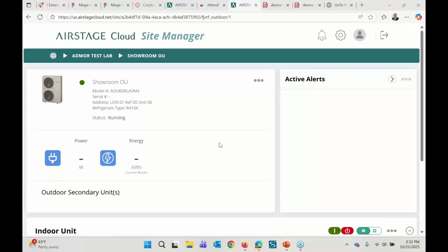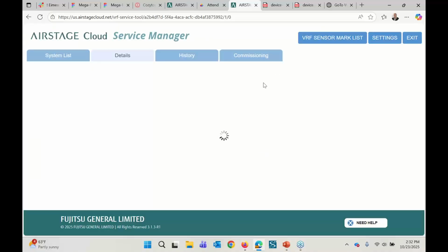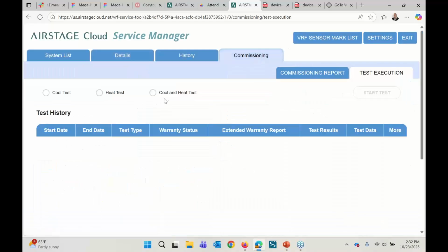Okay, there's a question about heat recovery systems. For heat recovery, what you need to do is use the cool and heat test. That's the acceptable answer. Most of you will do an RBU port test. That RBU port test is coming to AIRSTAGE Cloud. It's not currently running, but it is currently in development, so you'll be able to come in and, as part of your startup, do a branch port test with AIRSTAGE Cloud.